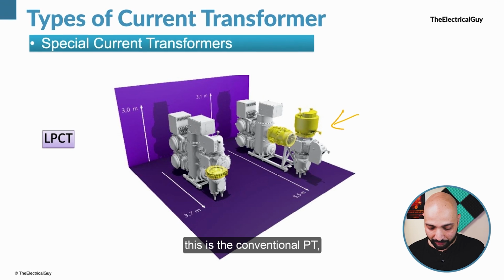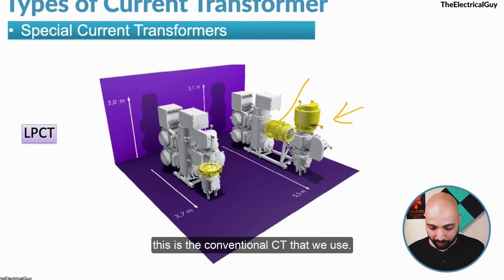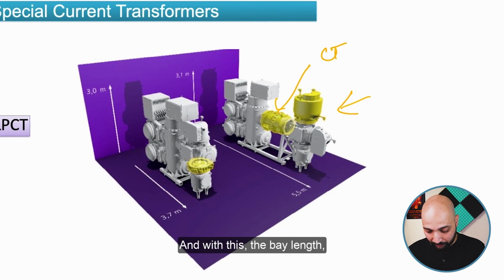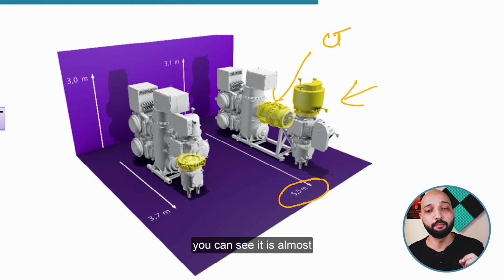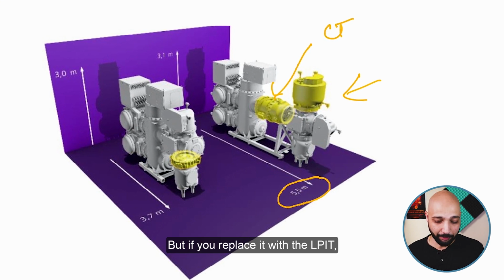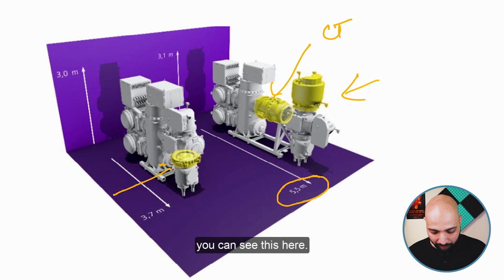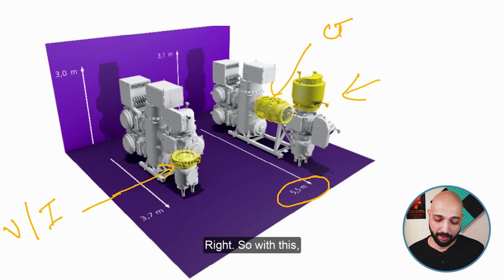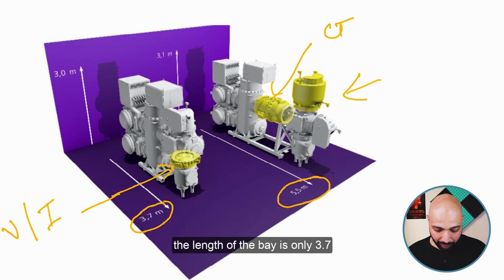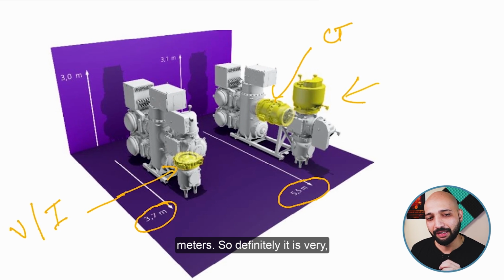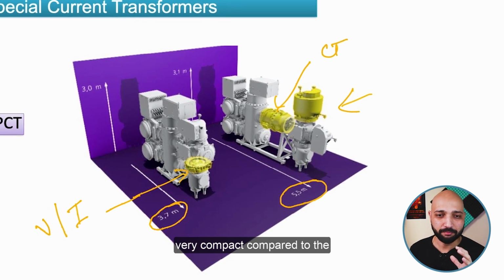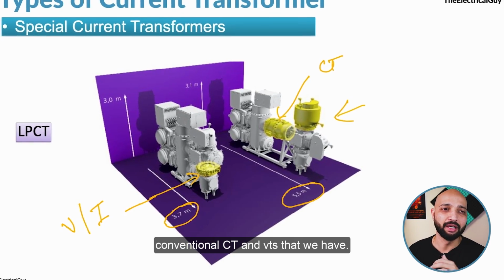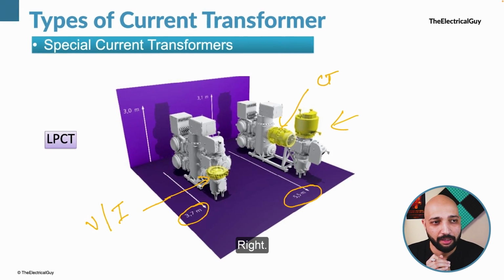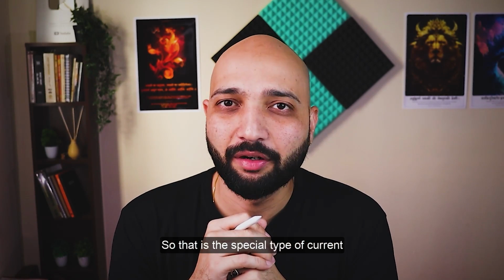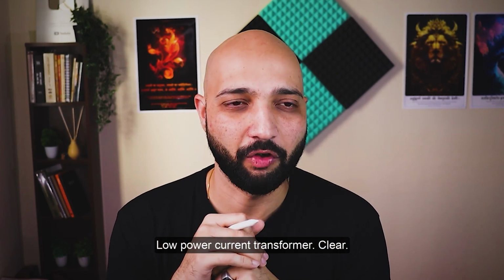On the right hand side here, this is the conventional PT, this is the conventional CT that we use, and with this, the bay length is almost 5.5 meters. But if you replace it with the LPITs, you can see this here. This can measure the voltage and this can also measure the current, right? With this, the length of the bay is only 3.7 meters. So definitely it is very, very compact compared to the conventional CTs and VTs that we have. So that is the special type of current transformer that we have, low power current transformer, clear?